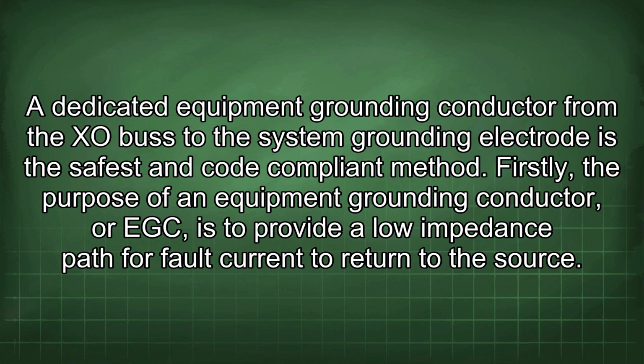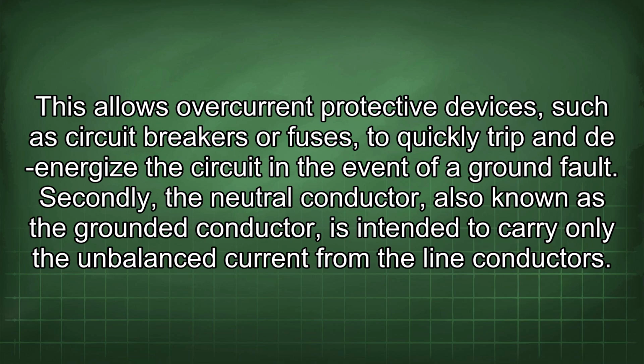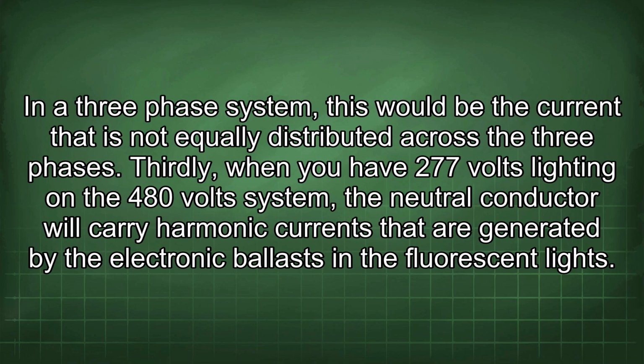Firstly, the purpose of an equipment grounding conductor, or EGC, is to provide a low impedance path for fault current to return to the source. This allows overcurrent protective devices, such as circuit breakers or fuses, to quickly trip and de-energize the circuit in the event of a ground fault. Secondly, the neutral conductor, also known as the grounded conductor, is intended to carry only the unbalanced current from the line conductors. In a three-phase system, this would be the current that is not equally distributed across the three phases.